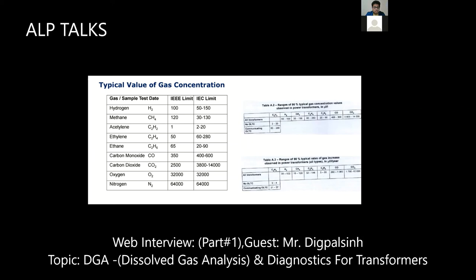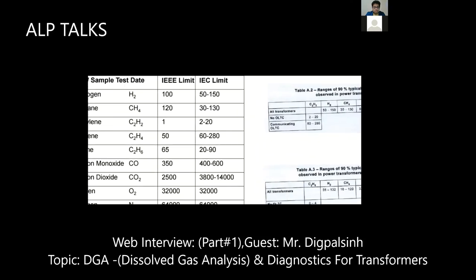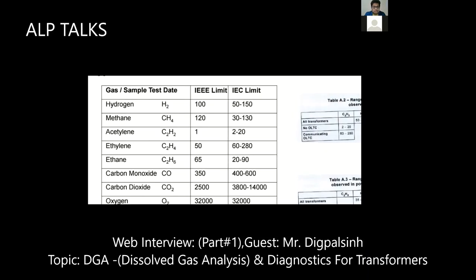And IEC says if your hydrogen is 50 to 150, then your transformer is healthy. If your transformer is newly manufactured and not yet commissioned, then IEC says your hydrogen should be 50. After 1, 2 or 3 years of operation it goes up to 150, and then there is no issue; you cannot say it is abnormal, it is normal. Then methane: IEEE says the limit should be 120 ppm, and IEC says 30 to 130. For a new, healthy transformer in the plant it should be 30, and after some years of use, up to 130 ppm is fine.